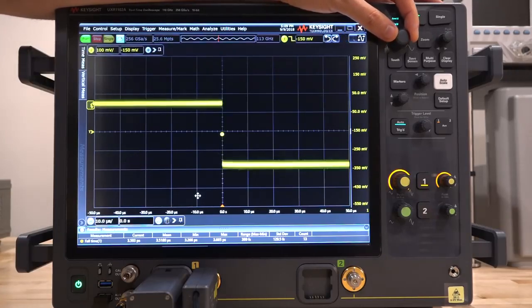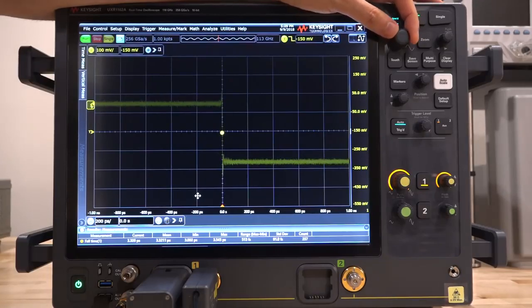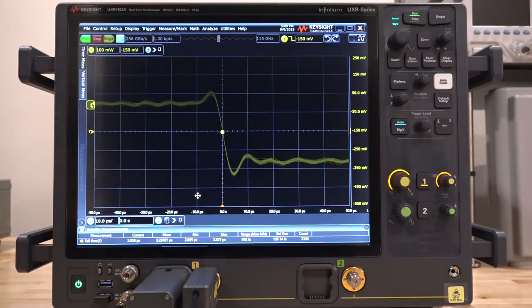So I'm going to go all the way down. Right now we're at 1 microsecond, keep zooming in, 5 nanoseconds, 1 nanosecond, and we're going to go here, 10 picoseconds per division. And check it out, we're looking at a 3.3 picosecond edge. That's how fast and how sharp those edges actually are, and this is why you're able to use this as a NIST calibrator. The exact group delay, frequency content, and phase information coming out of the calibrator has been transferred to the scope, and the scope is going to calibrate itself and change the coefficients required to match that exactly.